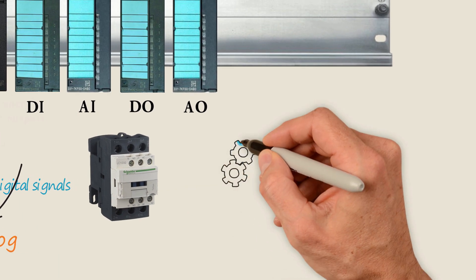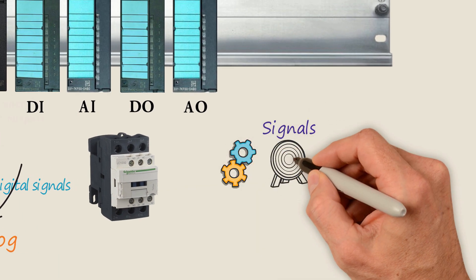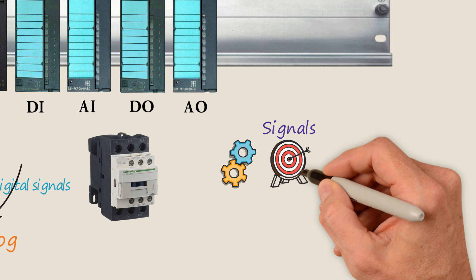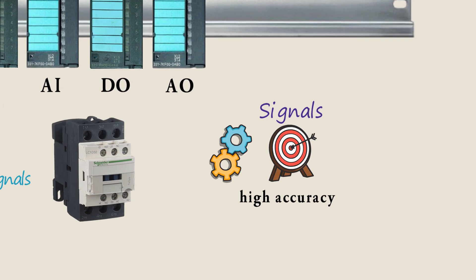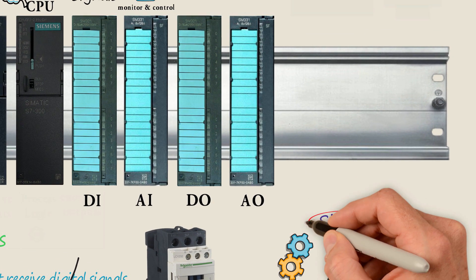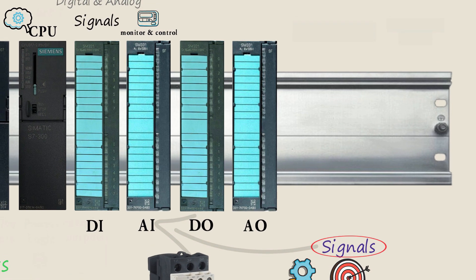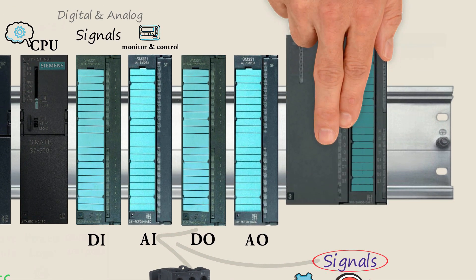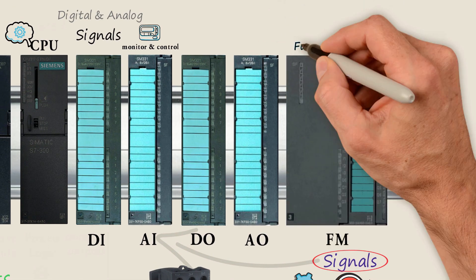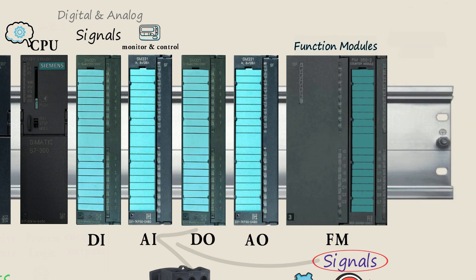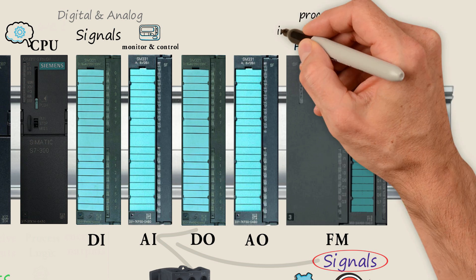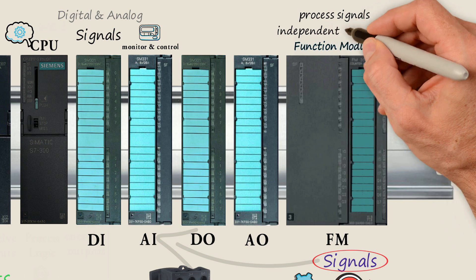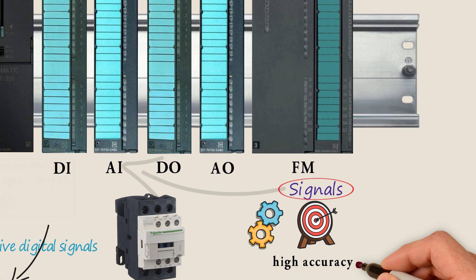Some applications require that particular signals are processed with higher accuracy. Those signals may not be connected to the standard IO modules, but instead require specialized modules called function modules, or FMs. FMs process signals independent of the CPU, therefore providing for higher accuracy.